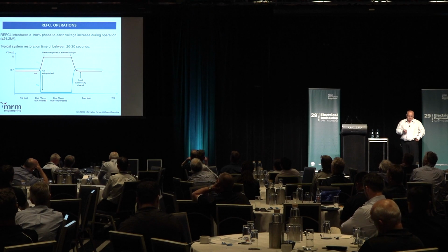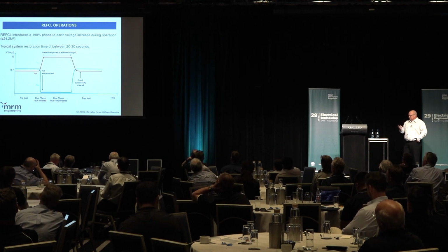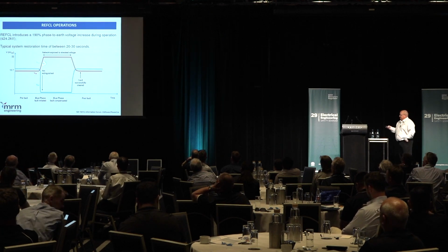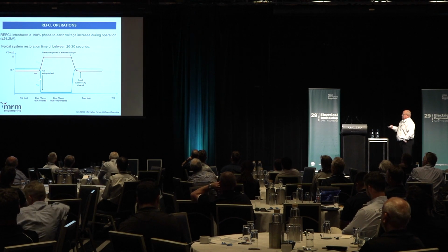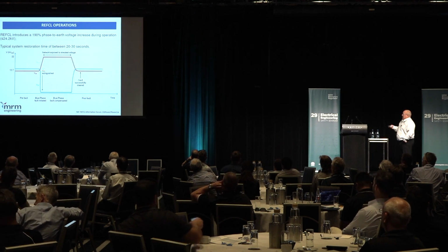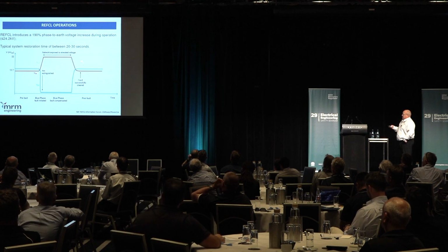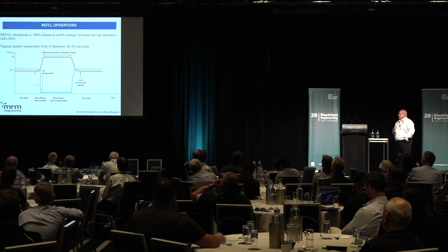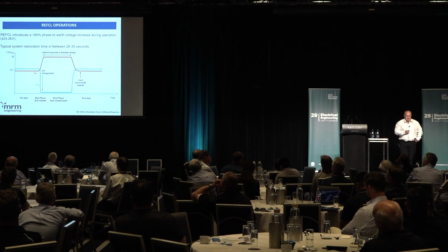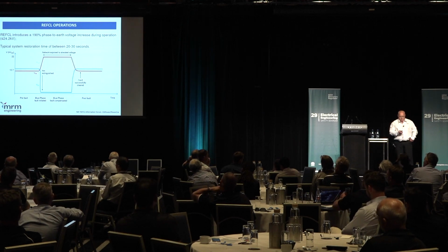So this is just a diagram of what they're planning to do. So standard operation, the blue phase goes to earth, the red phase voltage to earth goes high, and then it comes back to normal operation. But the key one here is this time here, 20 to 30 seconds for it to clear. So it's going to be holding that voltage for a longer period of time.